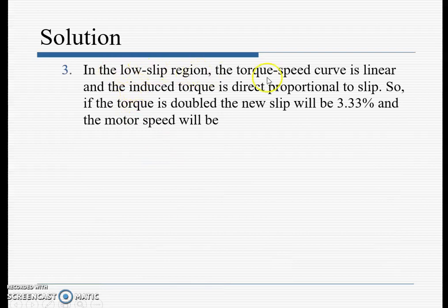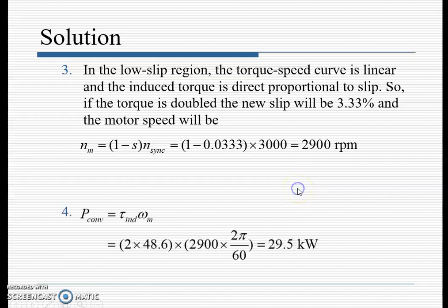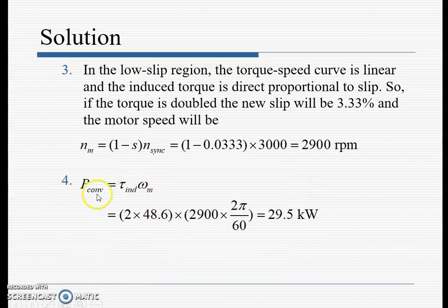In the low-slip region, the torque-speed curve is linear and induced torque is directly proportional to slip. If the torque is doubled, the new slip will be 3.33%. The new motor speed is n_m = (1 − s) × n_s = 2900 rpm. The power supplied by the motor at doubled torque comes out to be 29.5 kW.